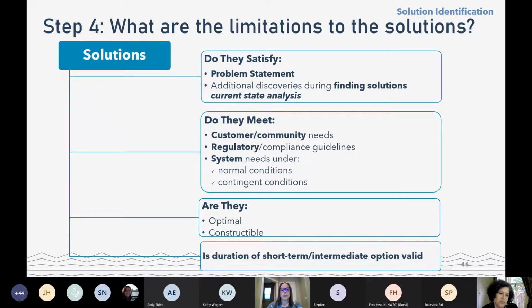Once we have our solution, we look at the limitations to the solutions. Does it meet the problem statement? Were there additional discoveries found? Something like the neutral current issue where we had the unbalanced loadings on the wires - that was something we discovered and needed to address on top of this new substation. Is the solution meeting customer and community needs, regulatory compliance guidelines, system needs under base case or contingency scenarios? Are they optimal? Are they constructible? And is the duration valid? We don't want to be going in year after year into a substation.